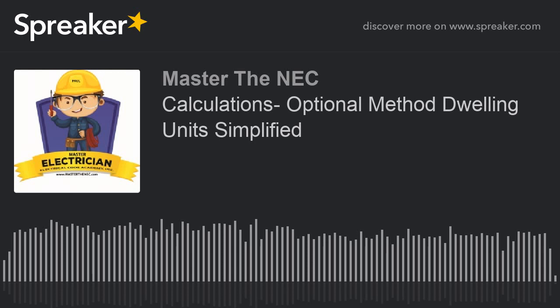First things first, if we look at 220.82, you'll see that we're talking about feeder and service loads. In our case, we're talking about service load today. It says this section applies to a dwelling unit having the total connected load served by a single 120/240-volt or 208Y/120-volt set of 3-wire service or feeder conductors with an ampacity of 100 amperes or greater.